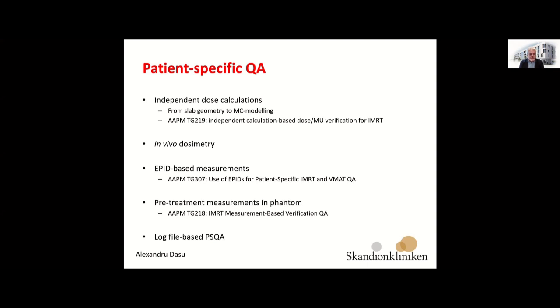EPID-based measurements have also found their use for advanced forms of treatment like IMRT or VMAT, because they allow a way of checking the capability of the LINAC to deliver the fluence recommended from the TPS. Pre-treatment measurements in phantoms are a very effective way of measuring the dose distribution, and this is something that we are using very much in proton therapy. However, it has the weakness that it doesn't take into account the handling of heterogeneity, for example, in a patient, or, in some cases, at least in proton therapy, you do not have the dose delivery at the recommended gantry angle, for example.